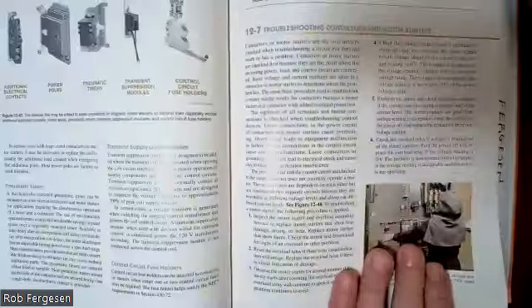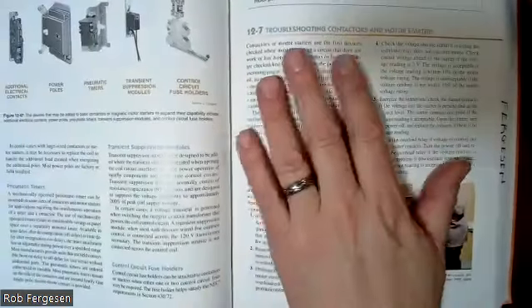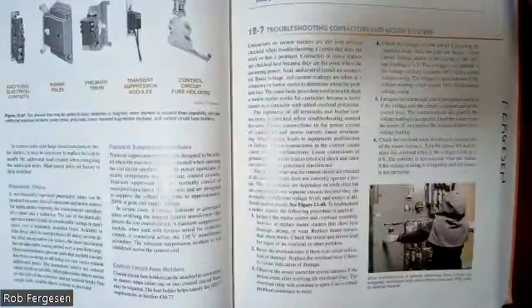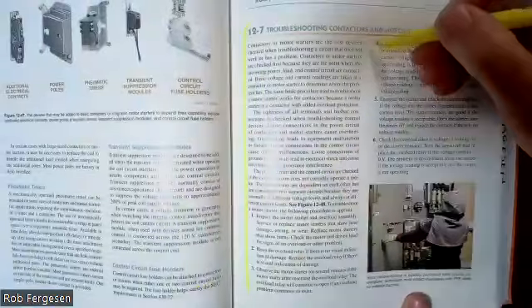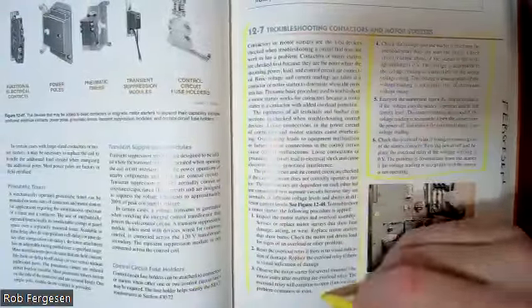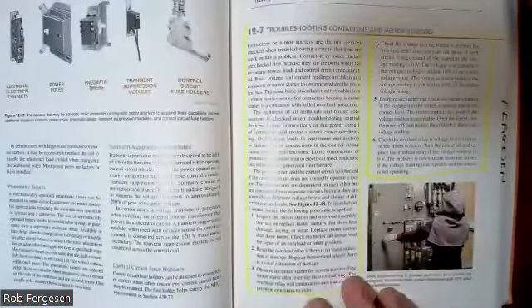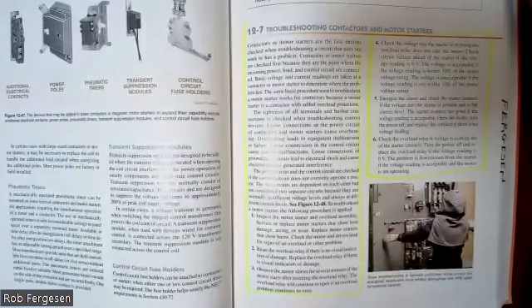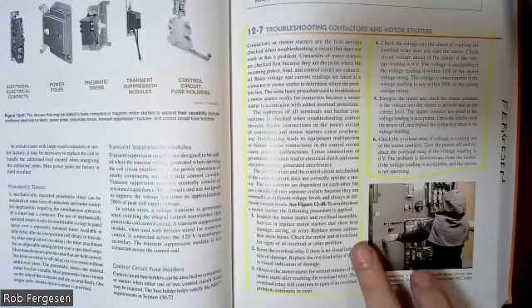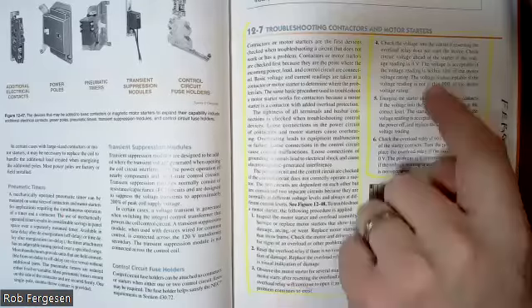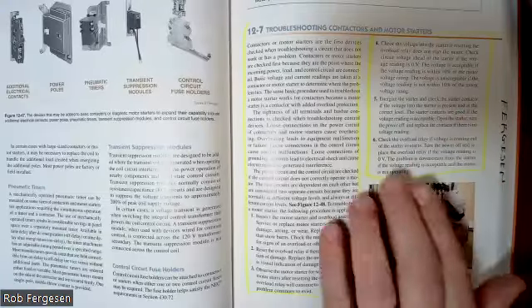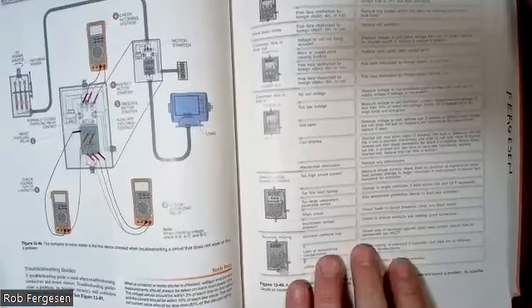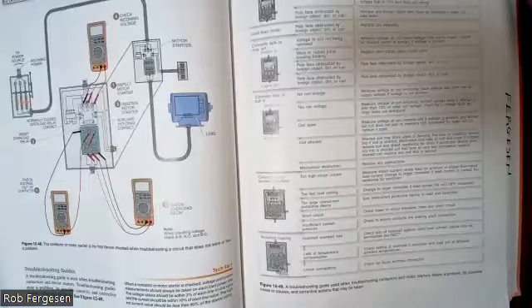And the last but not least section here is troubleshooting contactors and motor starters. And we're going to do a section on troubleshooting, and I expect that you guys will have this stuff read through and understand that. I'm not going to read it through with you, but it's very much common sense, you know. Inspect, reset, observe, check the voltage, check the starters, check the overload relays. Very much common sense. And there's a little one-page guide for you that you should be able to look up the problem and find the answer to it.